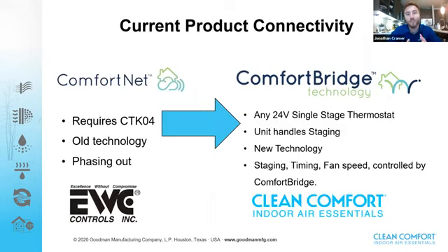Talking a little bit more about ComfortNet versus Comfort Bridge, as you know, that's a whole different presentation. I recommend you guys go check that out, because there is going to be a topic on that at the summit these past 3 days. But ComfortNet was kind of our older technology. What happened there was all the staging, all the algorithms on the fan speeds, all of that was configured on the actual CTK04. Well, now with Comfort Bridge, all of that is handled inside of the system itself. For example, the furnace and the air handlers are now handling the staging, the timing, and the fan speed internally. So with the CTK04, the thermostat controlled all that. With Comfort Bridge, all of that is in the furnace, air handlers, and indoor units. That is one of the big differences with Comfort Bridge: it's doing its own thinking, and it's learning, and the algorithms are all based off of itself.